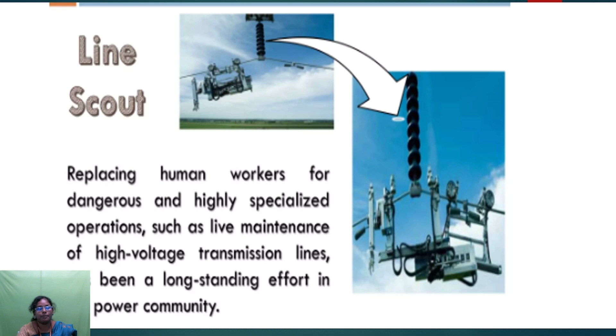This line scout robot has been designed to reach four conductors of a typical transmission line. One end of the arm is equipped with a point-able camera, and the other can hold a variety of tools for tasks such as high quality visual inspection, infrared inspection, checking the condition of splices by measuring electrical resistance, tightening and loosening bolted assemblies, and temporarily repairing broken conductor strands. For these issues we can use this line scout robot.